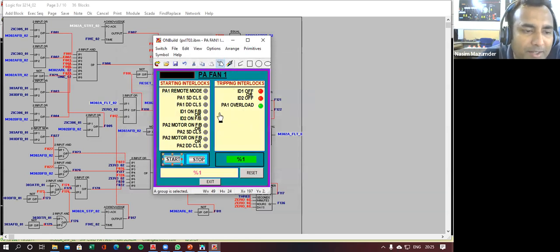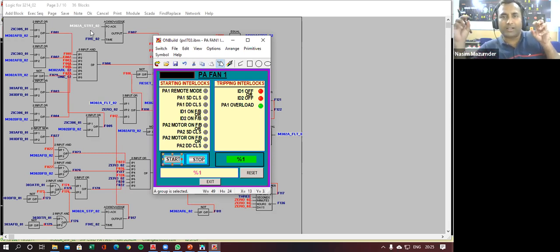Suppose this is a start command. Now the same start command I could give from some push button. If I press some push button, then this start command may come. Say yes or no. Yes. So suppose I have a push button in my hand, and if I press it, then this start command will come. Then what I have to do is attach this push button to some channel and configure that channel with some tag. That particular tag will become a hard tag.